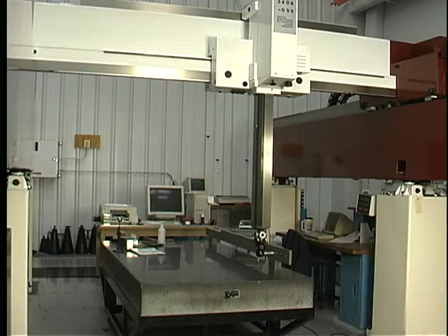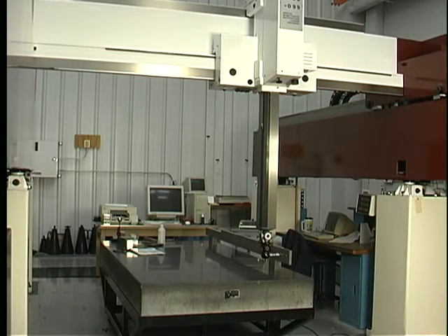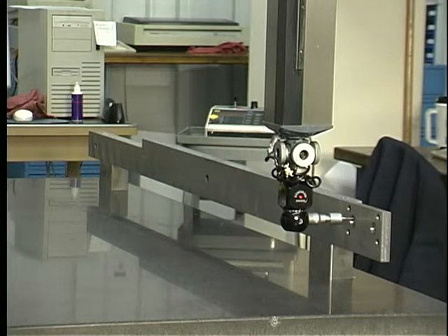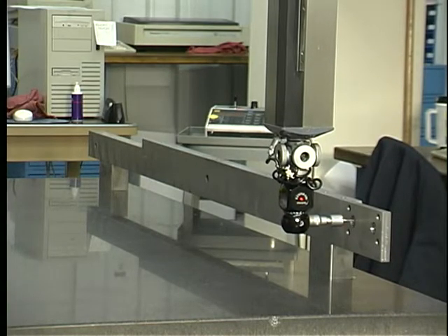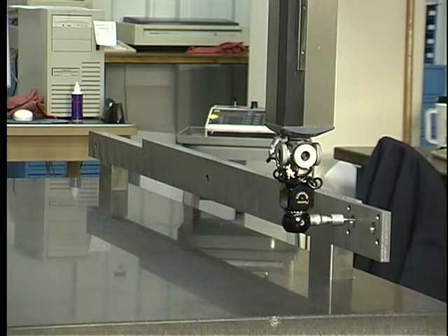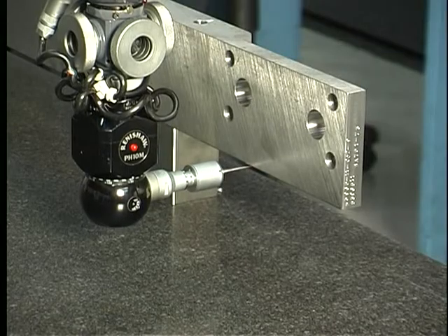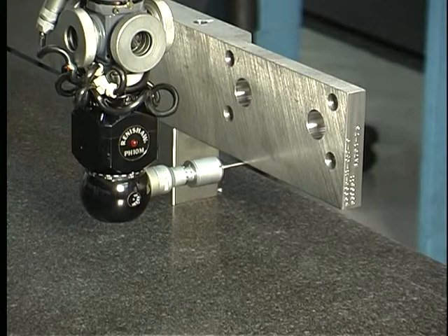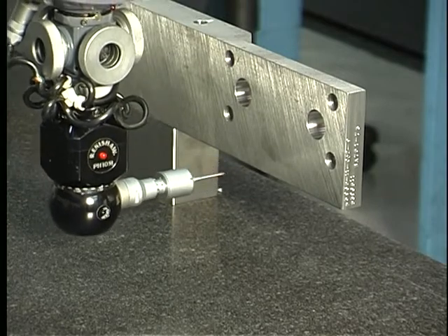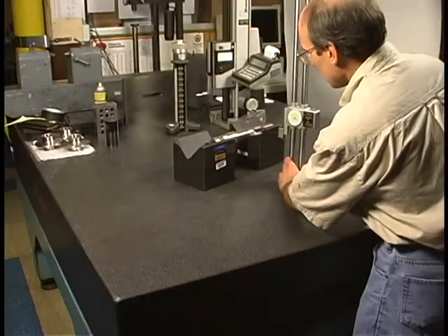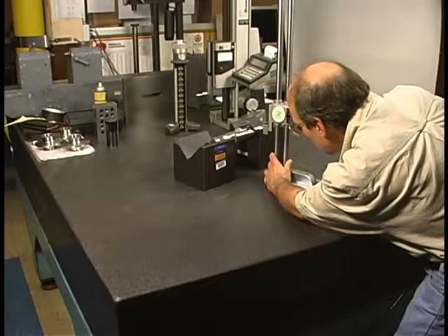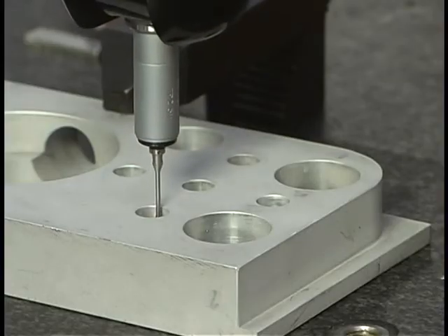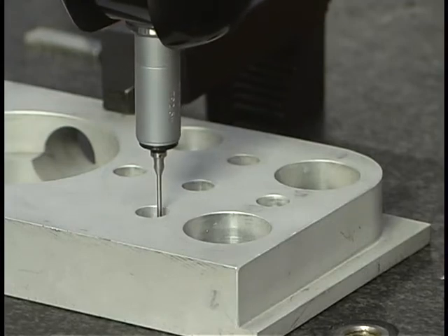Other CMMs are located in temperature controlled clean rooms. While a shop CMM is manually operated, larger CMMs have motorized control over the axis movements, which are then controlled by a computer program. These machines often have other features not covered in this lesson. Using a shop CMM can eliminate the need to use many other measuring instruments. It can also more accurately determine feature locations from surface datums.